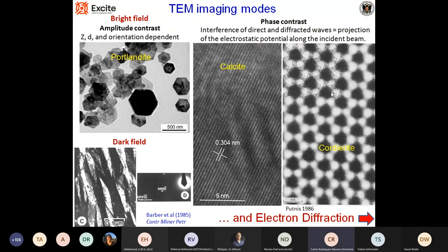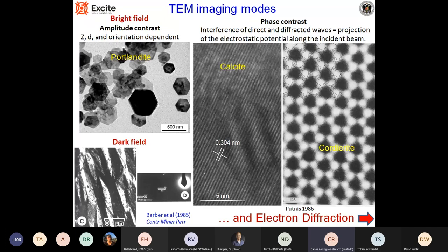The other mode for observing a sample is using diffracted beams. We can select a particular beam out of the diffraction pattern — for instance, the 006 beam of dolomite — and image the sample in what is called dark field, just through that particular beam. What we see is that the illuminated bright parts correspond to that particular orientation in the sample. Anything that is dark corresponds to a part of the crystal domain not oriented properly to produce diffraction — a completely different orientation than the 006 that produced the bright imaging.